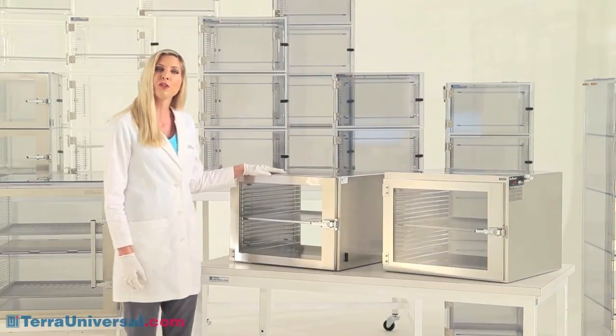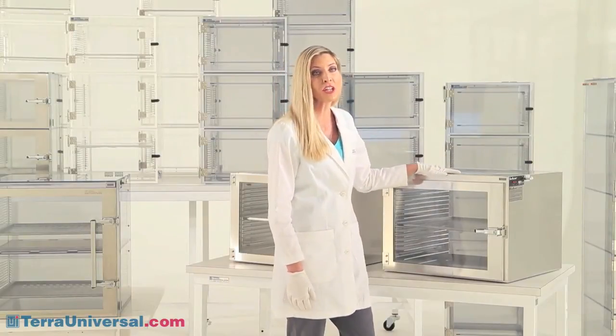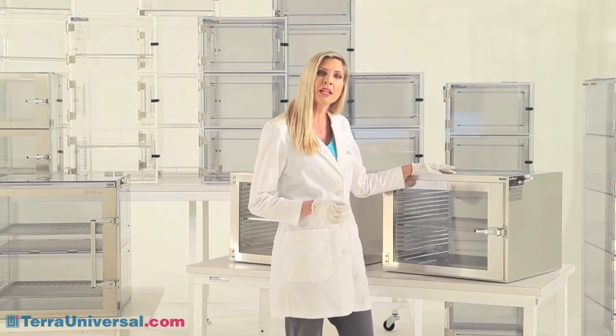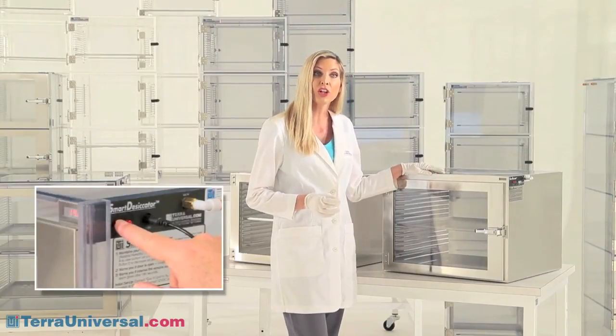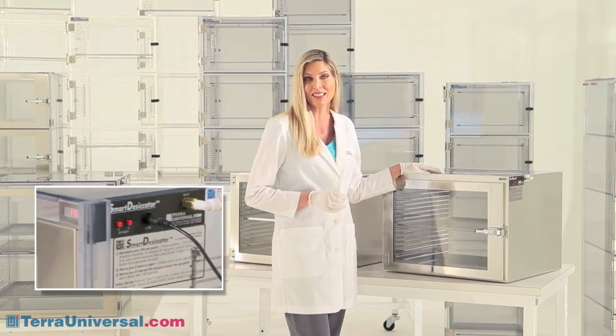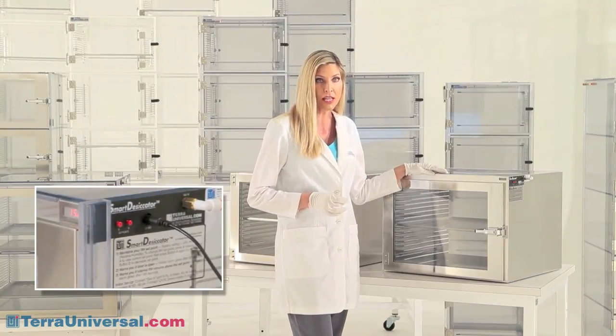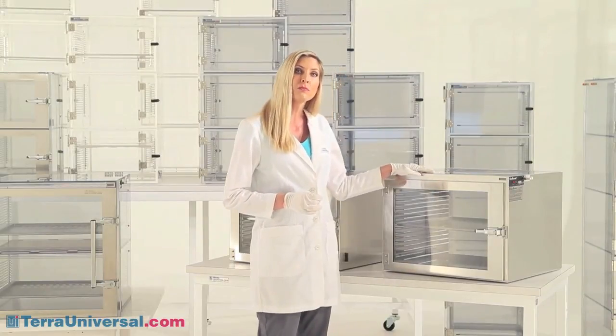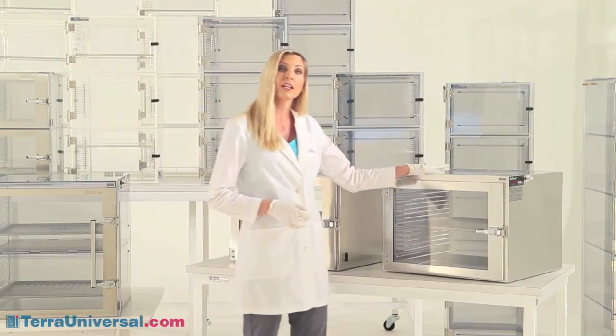The series 100 features Terra's unique all stainless steel lift latch. Terra's smart desiccator adds a turnkey humidity control system — this fully integrated double-wall system includes a humidity sensor installed inside the chamber and an LED readout of the current RH level. Push-button controls let you program a humidity set point in seconds, and the system regulates the incoming flow to keep the RH level below your set point without wasting nitrogen. The smart desiccator is electro-polished, giving it a shinier appearance than the series 100.